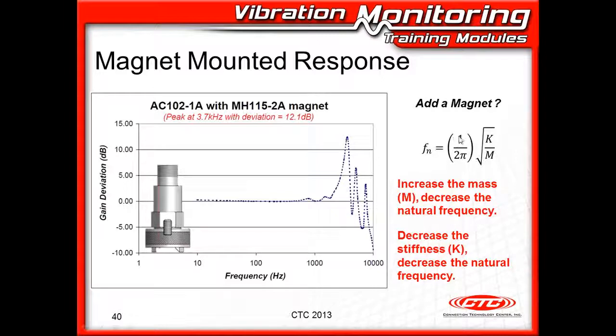And that's due to the natural frequency being equal to 1 over 2 pi times the square root of the stiffness divided by the mass. So we added a magnet and increased the mass, which decreased the frequency, and we decreased the stiffness, which decreased the natural frequency. So this is just a good example of what happens when you get something between the sensor and the machine. You're going to add mass, you're going to decrease stiffness, and the natural frequency moves down, and when that happens, the usable frequency range also deteriorates.